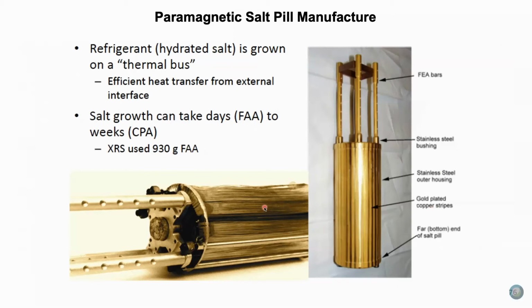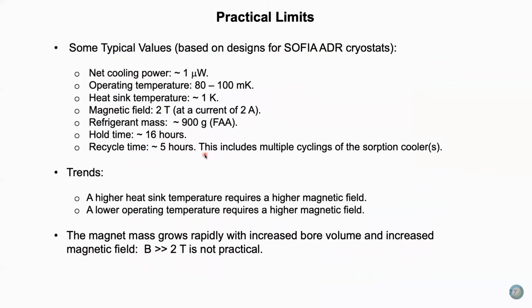Now, the paramagnetic salt pill is not just the salt itself. What makes it so complicated is that you have to get the heat in and out of it, and it's not a very good thermal conductor, so you have to have a thermal bus that looks something like this. And this is composed of very fine wires or ribbons of copper, and the salt, the refrigerant, is grown on this bus, and that can take days to weeks to do properly. XRS, this is something we'll be talking about in a couple of slides, uses 930 grams of FAA. It's the same materials used in the HAWC ADR as well as the HIRMES ADR, about the same amount of refrigerant as well, around 900 grams.